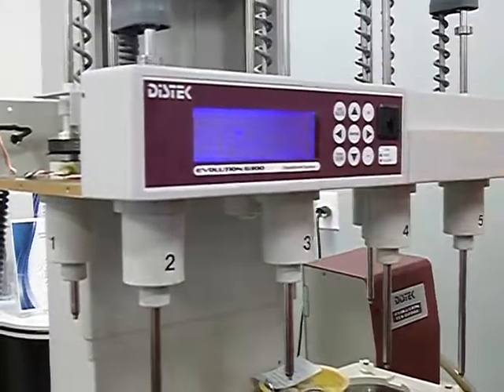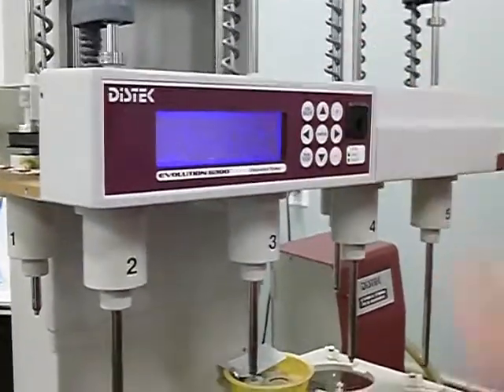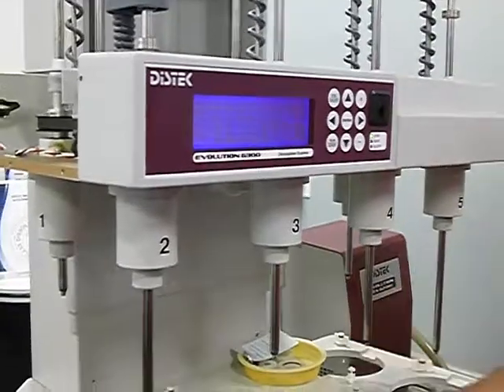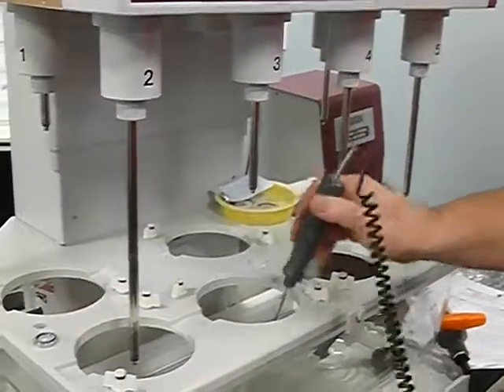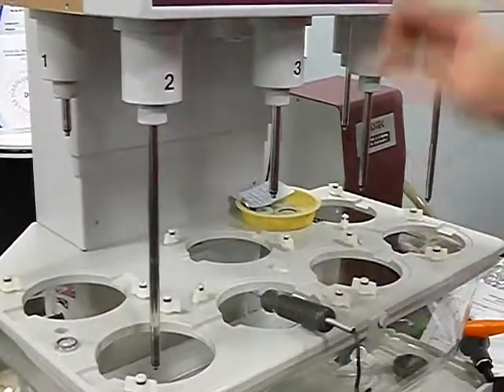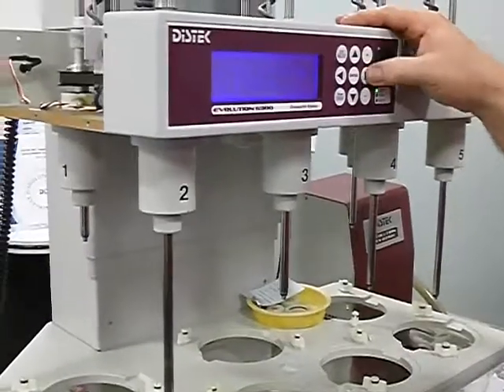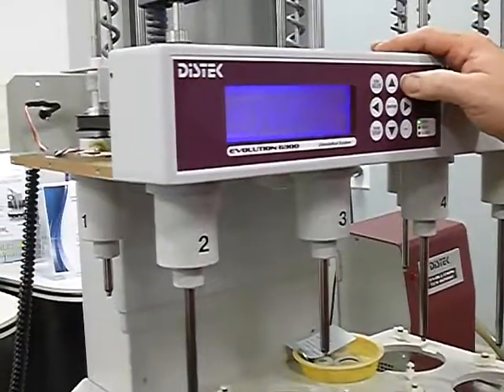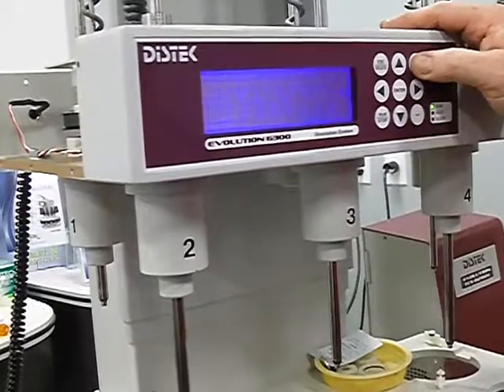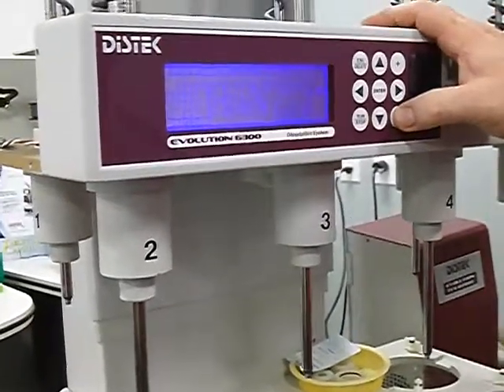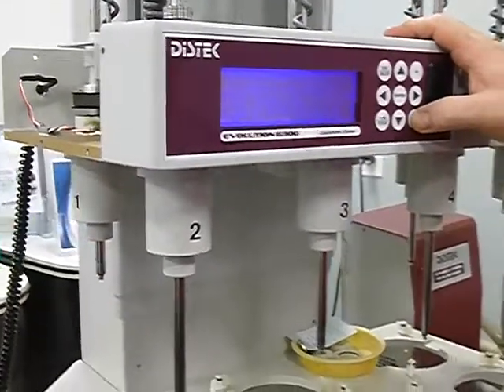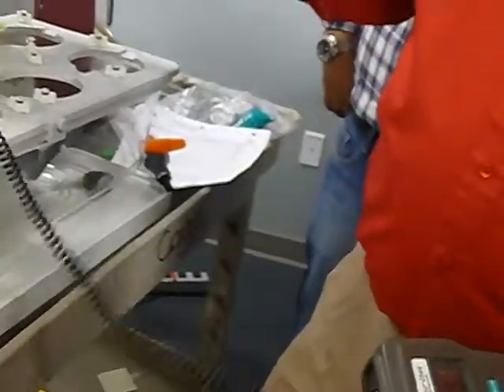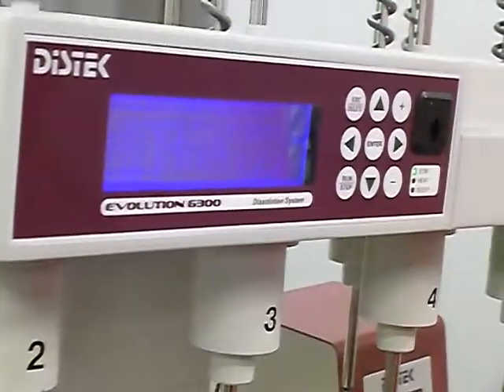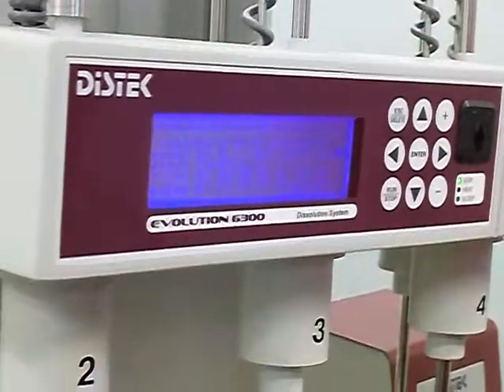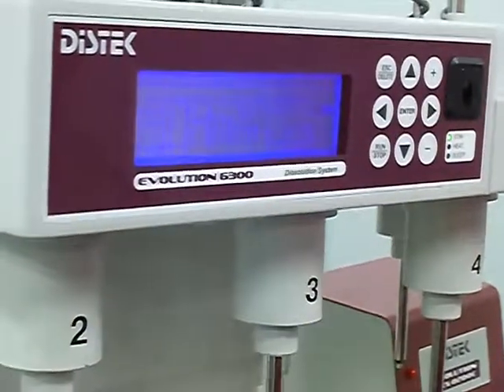So if I wanted to adjust it, I simply would come in here, put my reference temperature inside the media, each one of the vessels, and simply turn it up. And this will actually go by hundredths. So you can match exactly what's on here, because this actually goes out to 100ths also. You simply put the number in it. Low temperature. You got to do a low calibration and then do an upper calibration. So better both. So I usually do both.